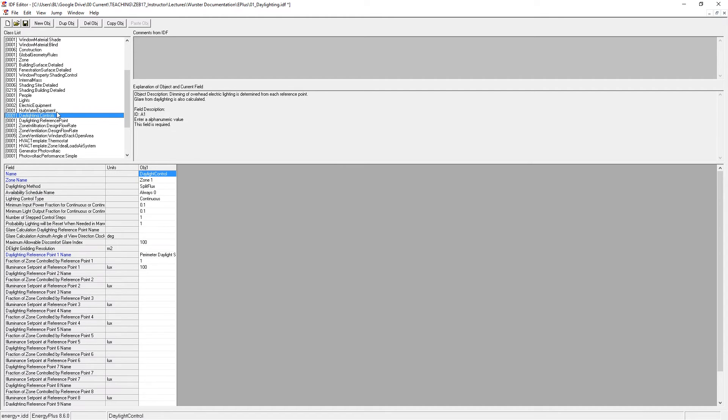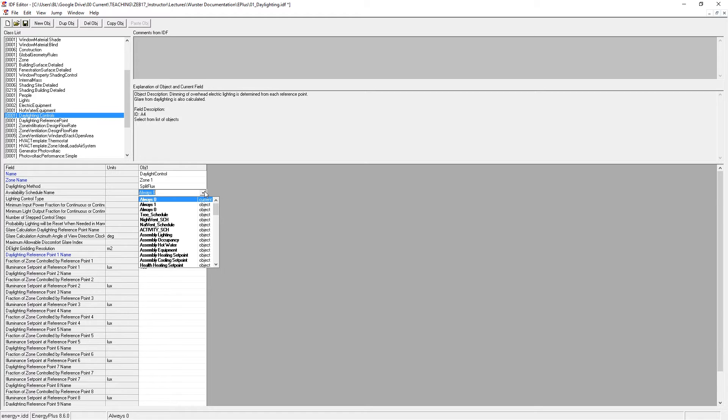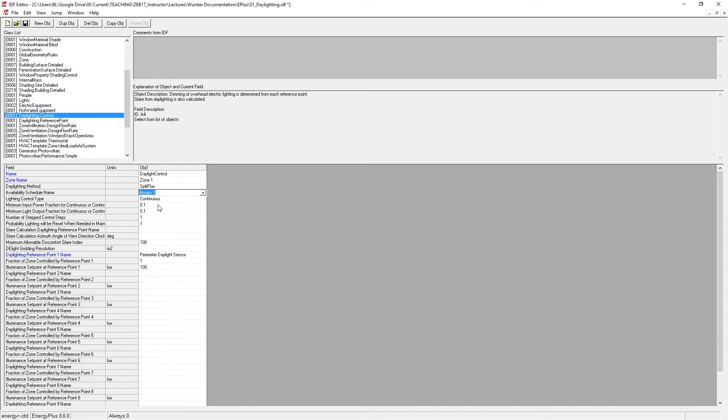Now we can go into daylighting controls and turn that sensor on. By default, you'll see the availability schedule is always zero or always off. It's always going to multiply the schedule by zero. So you'll get zero. If we turn it on to always one, now the daylight control will be on.